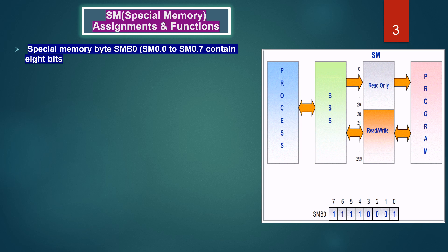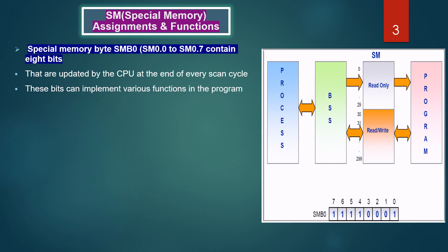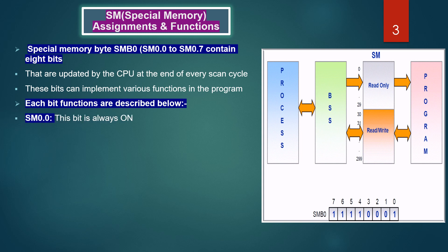In this slide we are going to discuss the special memory bytes. The special memory bytes start from SM 0.0 to SM 0.7, which contain 8 bits that are updated by the S7-200 CPU at the end of every scan cycle. With these bits you can implement various functions in your program. SM 0.0: this bit is always on.